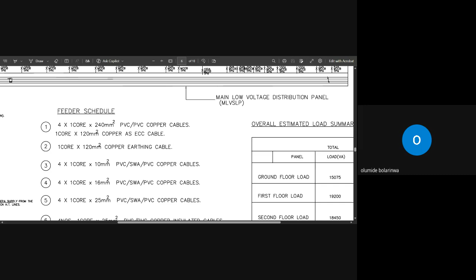Sorry, can you come again with that, sir please? I said someone said it is 4 core by 240 mm cable. I said no, it is a single core, it will now be 240 mm single core, and it will run in 4 places. That's why they call it 4 runs. Sometimes you might see 8 runs. It shows that if your total length of 1 core by 240 mm cable is 100, you slash it by 4, so it will now be 400 meters, not 4 core. 4 core means in one cable you'll see 4 different cables inside, but when you see 4, it means if it is 100 meters, it will be times 4, it will now be 400 meters. Do you understand my explanation?